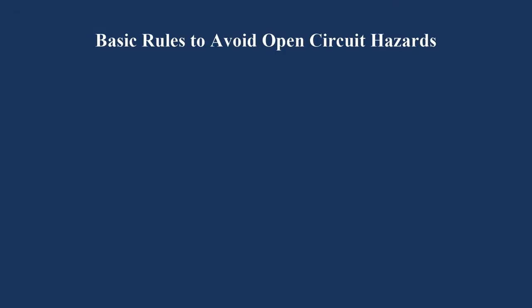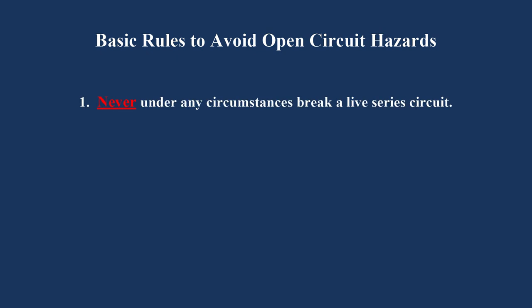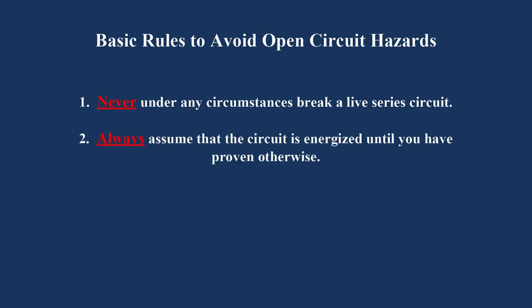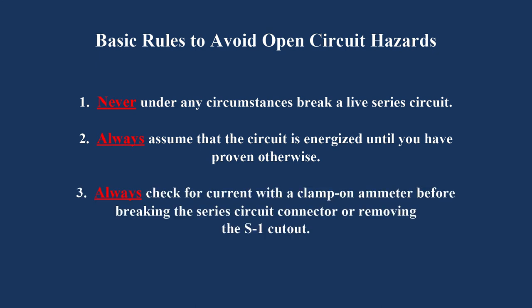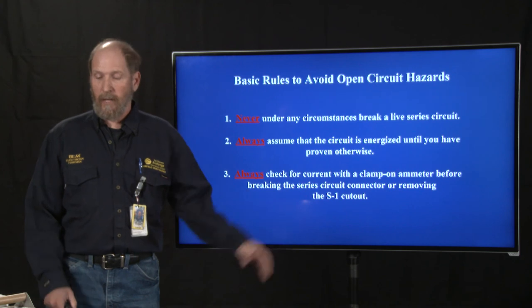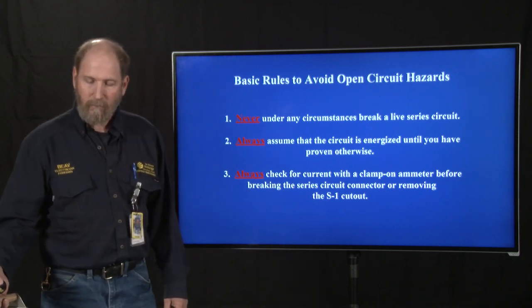So there's some rules to avoid open circuit hazards. And these are what I learned with. The first is never under any circumstances break a live constant current circuit. The second, assume that every constant current circuit is live until it's proven otherwise. I think of it as a gun. It's always loaded until you prove otherwise and treat it as such. And lastly, always check the current in the wire with a clamp-on ammeter before breaking any constant current connection, and or the S1 cutout in the regulator room.